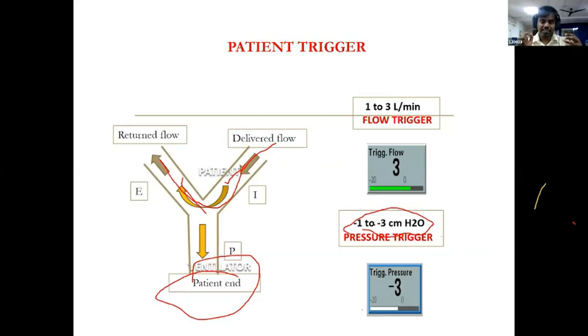The ventilator will assess when the trigger is happening. For a flow trigger, the normal value is 1 to 3 liters per minute, and we can keep 2 liters also. I'll tell where you have to do the settings. 1 to 3 is the normal value for flow trigger or pressure trigger, both the same, -1 to -3. If the trigger sensitivity is -5, the ventilator won't assess your trigger. So you have to be very careful. If somebody manipulated it by mistake and the trigger sensitivity is -8, the ventilator won't assess the patient trigger and will continuously be giving the breath.